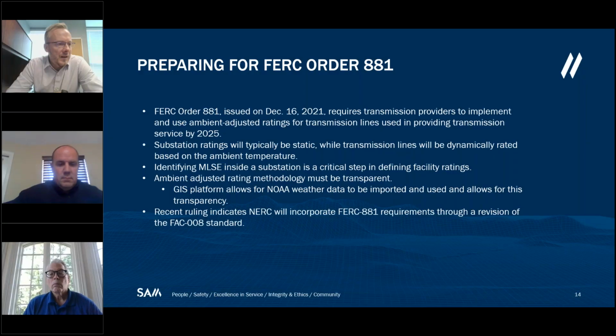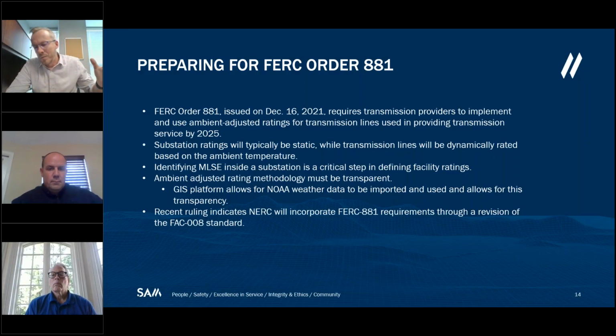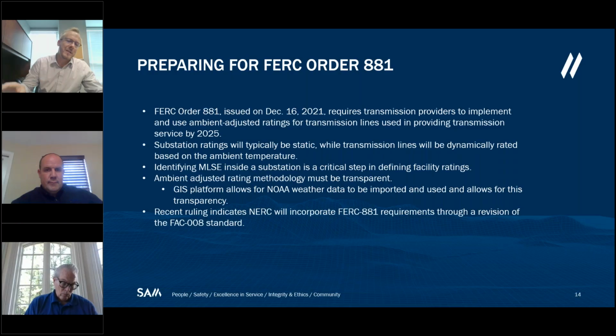The key part of this FERC 881 will be bringing in weather data from NOAA, probably. NOAA links and data is what FERC has identified as the key source. You can use Met towers and other technology, but to accurately rate your facilities based on ambient temperature in a given area, you'll need this information hosted on a GIS platform. Measuring elements in the field and having them geospatially located is key to the success of your FERC Order 881 implementation.